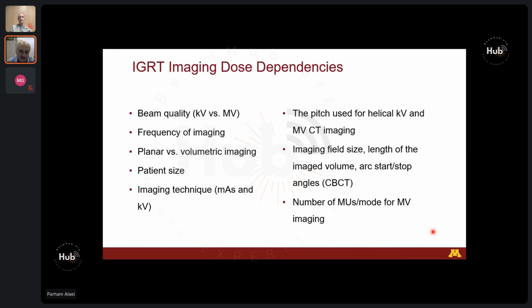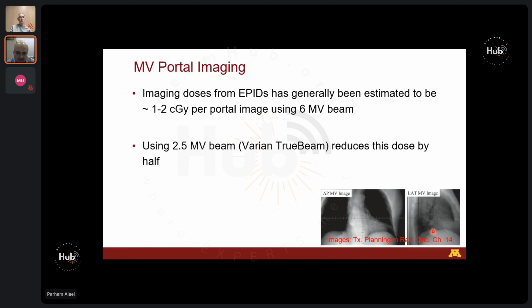So portal imaging is something that we've done since the onset of radiation therapy. And we've always estimated the dose from portal imaging with a megavoltage beam to be about 1 to 2 centigray per image, using a 6 MV beam. If somebody has access to a 2.5 MV beam, like on newer variants of TrueBeam, that would reduce the dose by half. So I strongly suggest using that if anybody has it on their unit. Actually, the image quality is slightly better too because it's low energy.